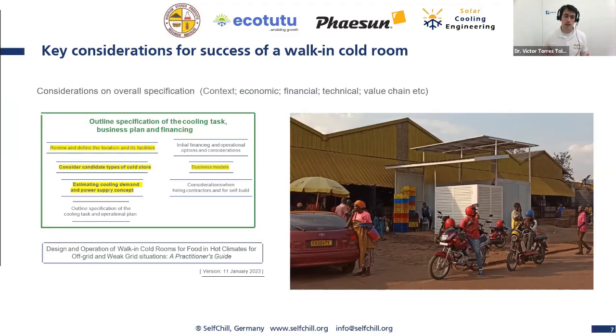Something else I want to let you know: because this is a solar power system, the ambient temperature also has an effect on the cooling demand and on the efficiency of the refrigeration machines. The location where you are is going to be crucial, depending on the city. If it's, for example, at the seaside with very warm temperatures, you will have higher cooling demand, less efficiency, more cost, more PV panels, and so on. Very important to figure out at the beginning what we are going to do with the cold room, and where the cold room is going to be installed.